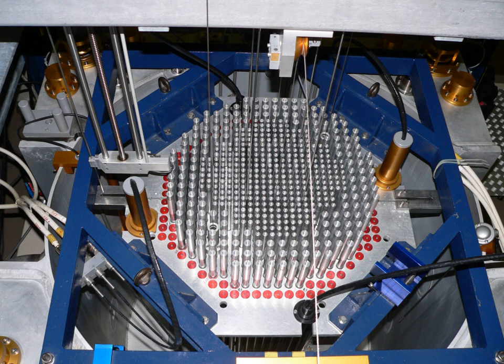Pressurized Heavy Water Reactor: A Canadian design known as CANDU, these reactors are heavy water-cooled and moderated pressurized water reactors. Instead of using a single large pressure vessel as in a PWR, the fuel is contained in hundreds of pressure tubes. These reactors are fueled with natural uranium and are thermal neutron reactor designs. PHWRs can be refueled while at full power, which makes them very efficient in their use of uranium. It allows for precise flux control in the core.